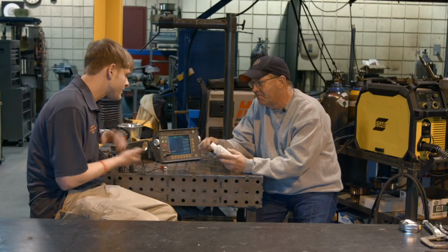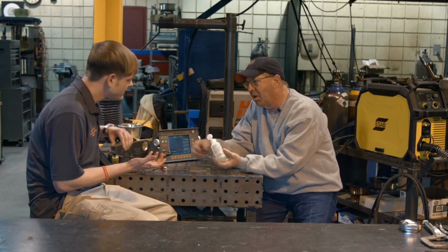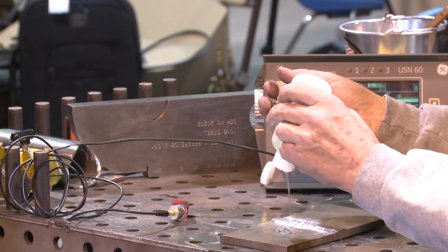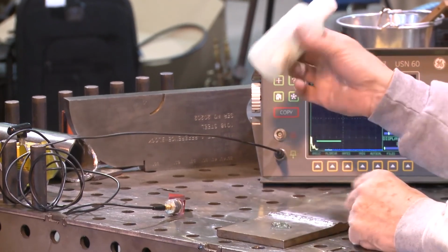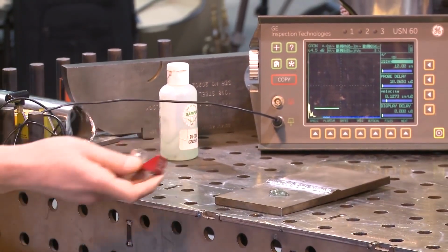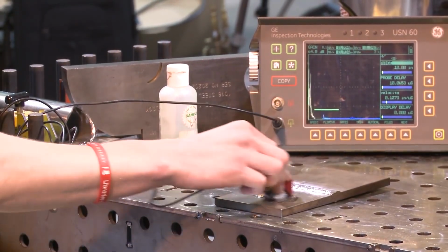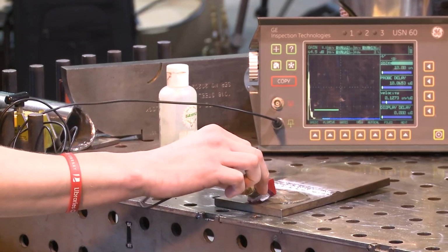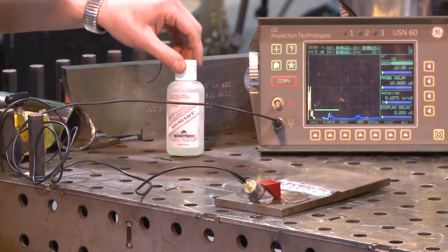Because ultrasound does not travel through air very well. So what do you do? Just put a blob on the material? Yes, sir. You don't need to get real dainty with it either. Yeah. Kind of like that? Yeah, I'm good at this already. I can nickname that welder's jelly right there. Yes, sir. So when I come down on this material, I want to spread this out nice and thin because I don't want any air under the transducer. I want a good couplant. Well, this is technically termed couplant.